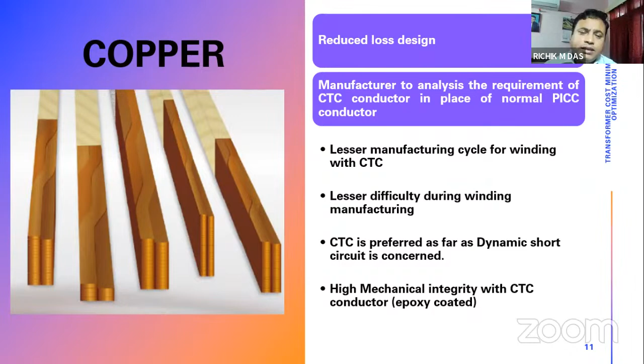So manufacturers should adopt the CTC type of conductor for high current rating windings, so that their design margin will be more, their design will be more rigid, and it can withstand short circuit force nicely. It will also reduce the manufacturing time cycle. So the manufacturer has to see this; it will help a lot in their design.